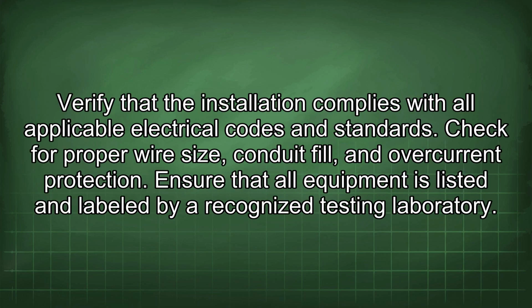Verify that the installation complies with all applicable electrical codes and standards. Check for proper wire size, conduit fill, and overcurrent protection. Ensure that all equipment is listed and labeled by a recognized testing laboratory.